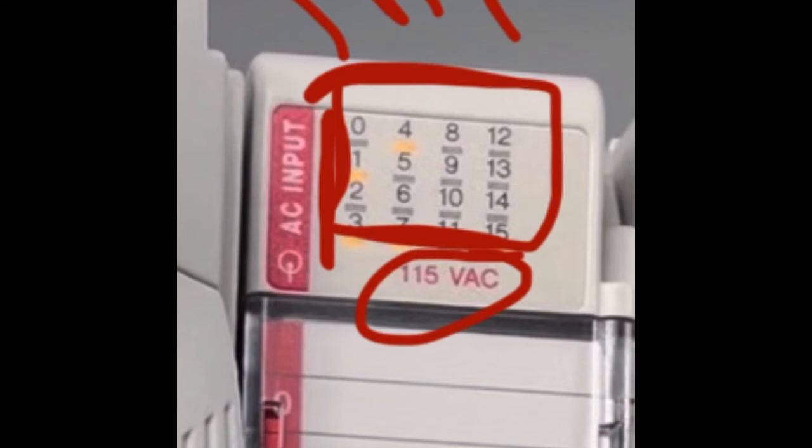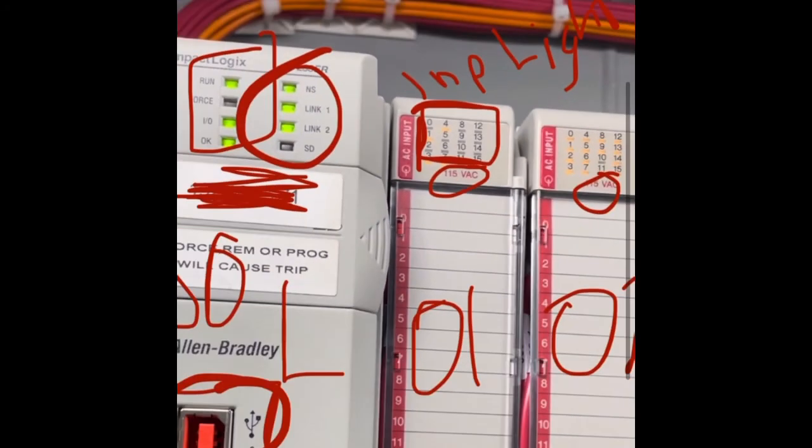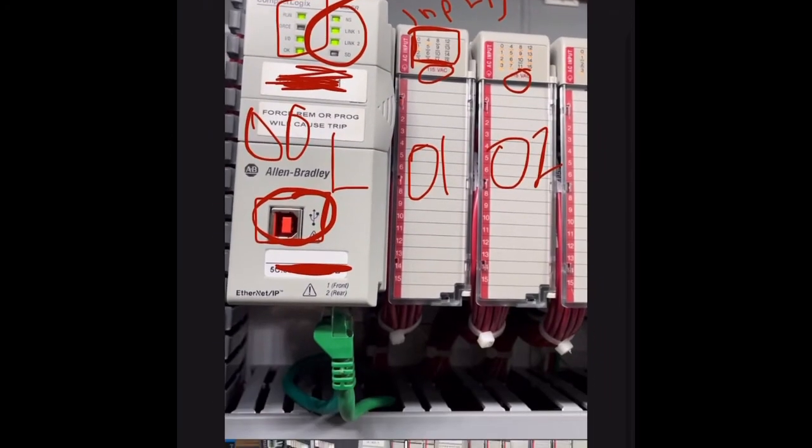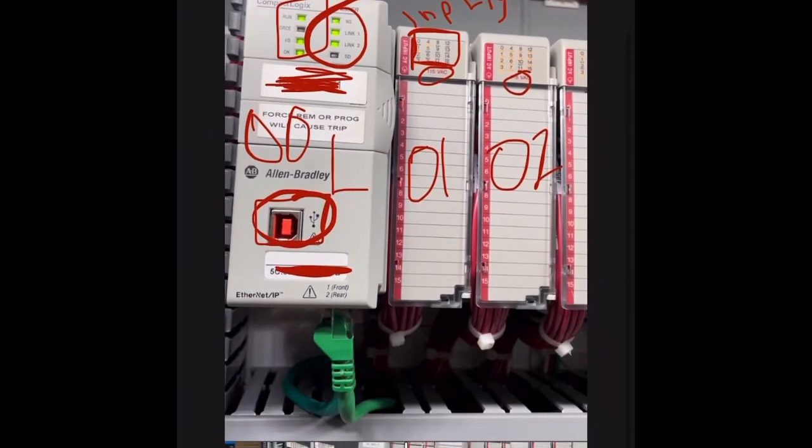So here you'll see slot 1, channel 0 is off, that means there's no voltage present at the input terminal, so there's not 115 volts there. And then you'll see here slot 1, channel 4, the light's on, so that means there is voltage present at the input terminal. So kind of a way to help you troubleshoot a little bit without getting online.